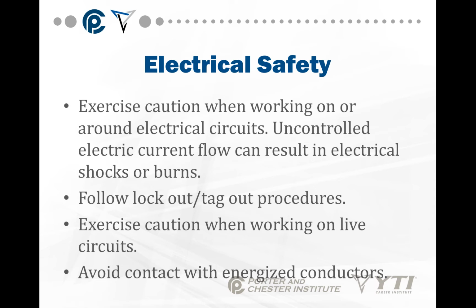We also deal a lot with electricity through this course. We need to exercise caution when working on or around electrical circuits. Okay, an uncontrolled electrical current. In other words, if you stick your hand or a tool that your hand is holding into a live circuit, you can actually have that current flow through your hand, down through your body, and depending on voltage, it can cause shocks or burns. Everyone does not react the same way to electrical. Okay, follow lockout tagout procedures, which your instructor will talk to you about, and exercise caution when working on live circuits. You do not want to come into contact with energized conductors. So if you're using a meter or another tool inside a live circuit, which you will have to as an HVAC technician, you just need to avoid contact directly with those energized conductors.